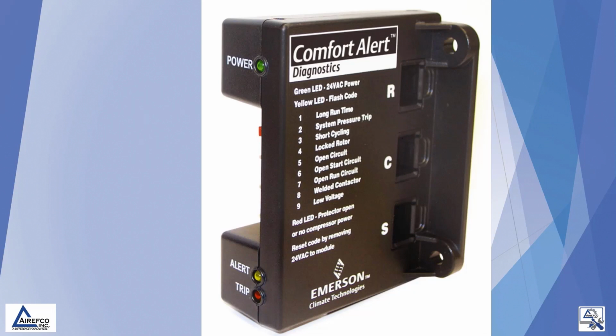This is the Emerson Comfort Alert diagnostic device that you may find installed on many HVAC units. It is an extra protection device for the compressor which monitors the voltage to the compressor at all times and will flash a code or lock out whenever there is a problem.